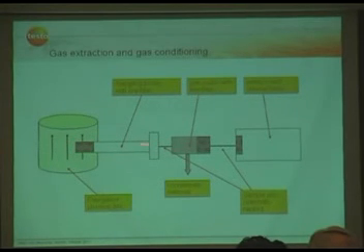And then the flue gas goes to the gas cooling system to remove the condensate of the flue gas. This can be an external device, or this can be an internal integrated system like a Peltier chiller, a small one.